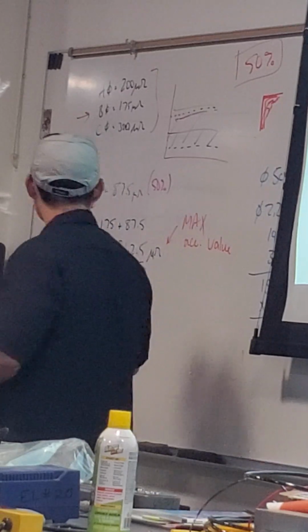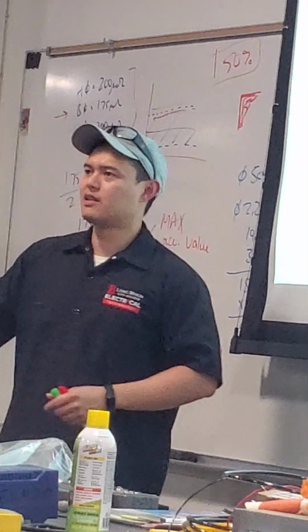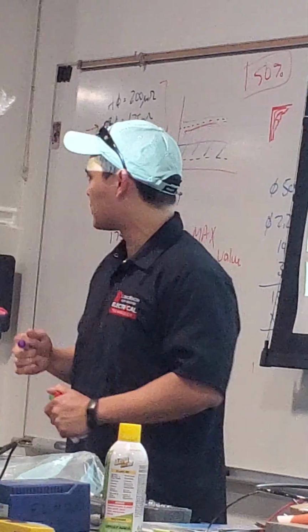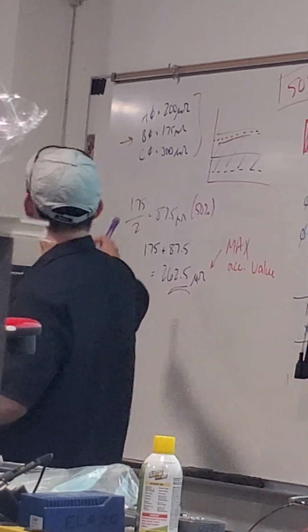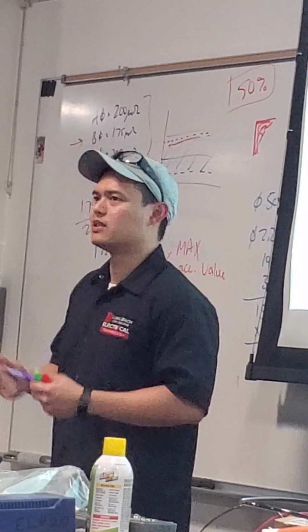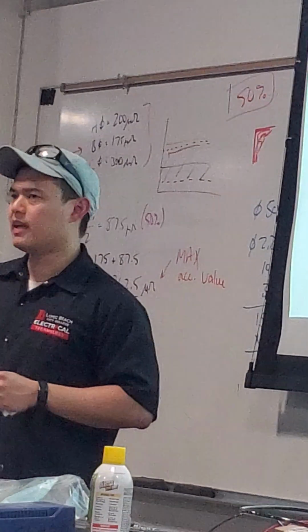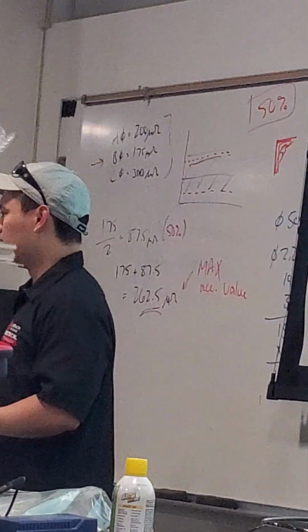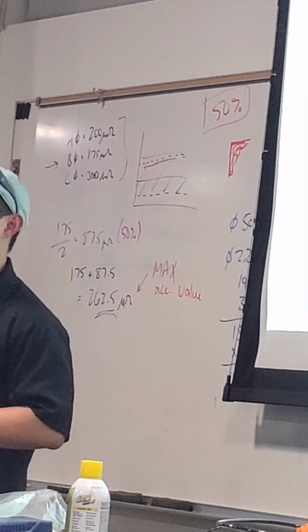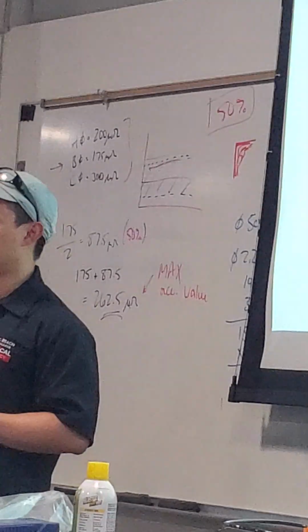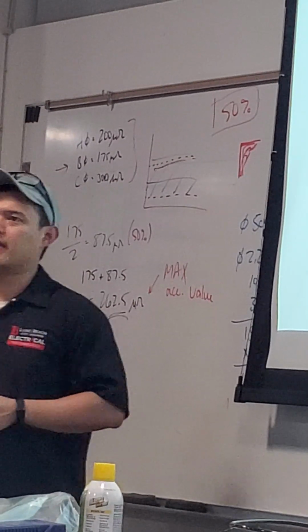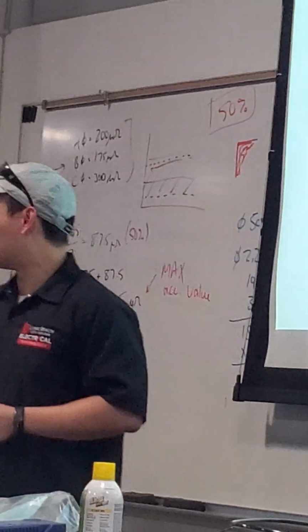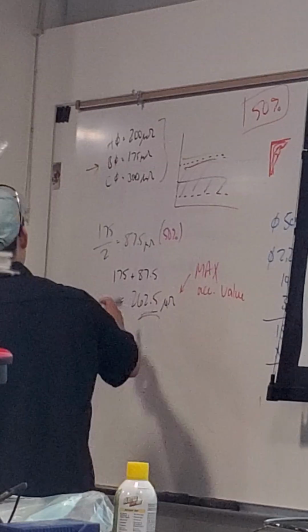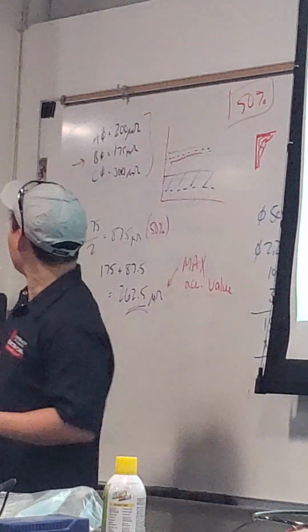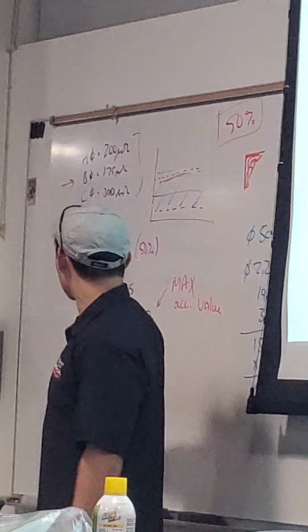So in this case, what is the major difference? 300 is too high. So as a qualified NETA electrical test technician, what can you conclude in words about C phase? It could be a loose connection, because resistance goes up with a loose connection. And with a loose connection, heat also goes up, and heat causes damage. Good — you nailed it: C phase shows a possible loose connection and is outside of the 50% rule. Something like that is gold.